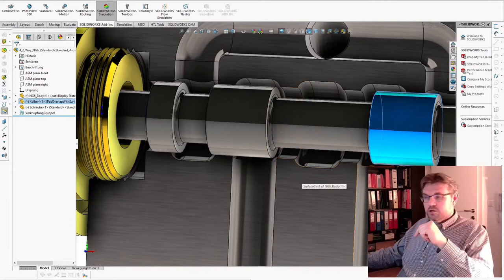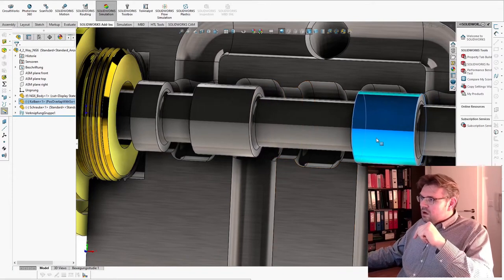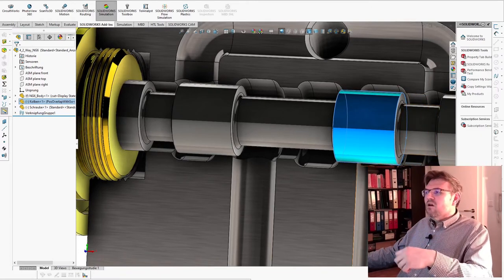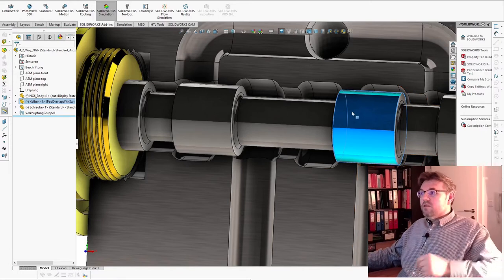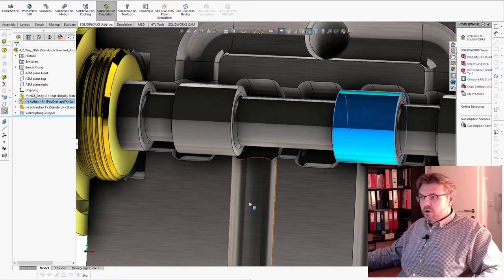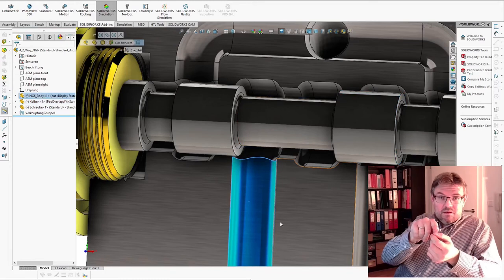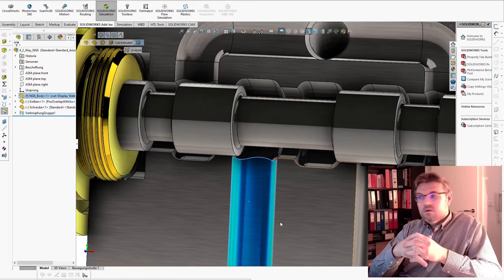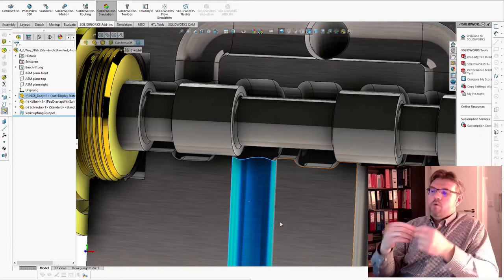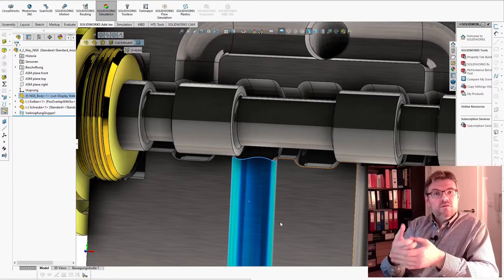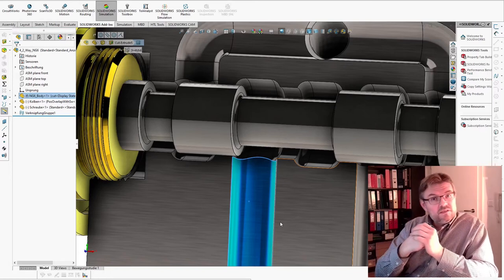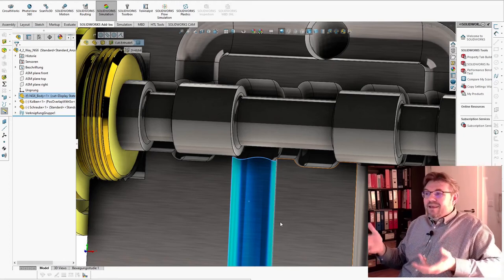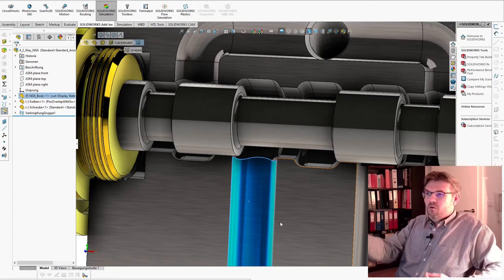Now both are under pressure. And now I open the relief line, the tank line on the other side. So with this piston, I first put the pressure on the element and then open the relief line. This would be pressure pre-opening. There is also a different piston where I first open the relief line, the tank line, and then put the pressure to the other side. Relief pre-opening.